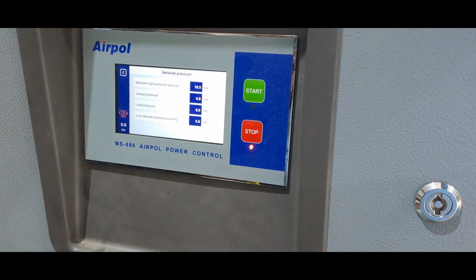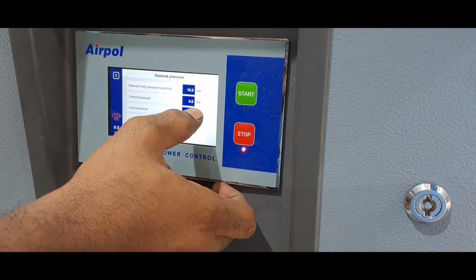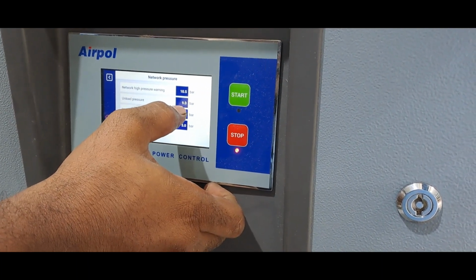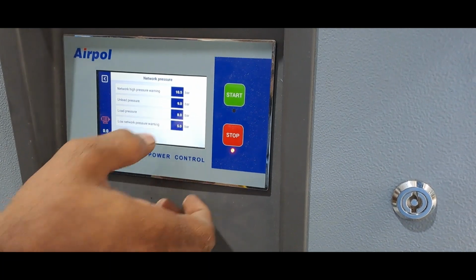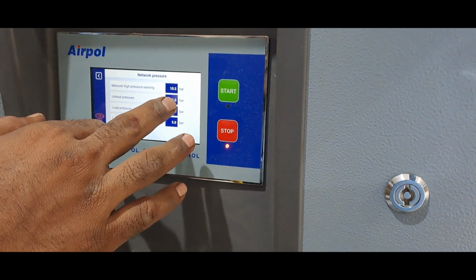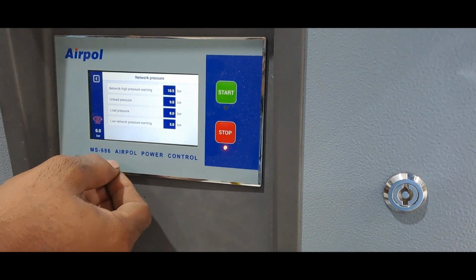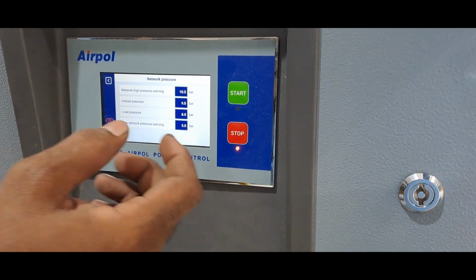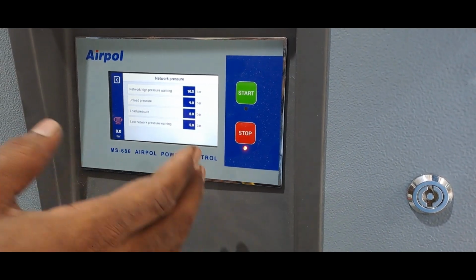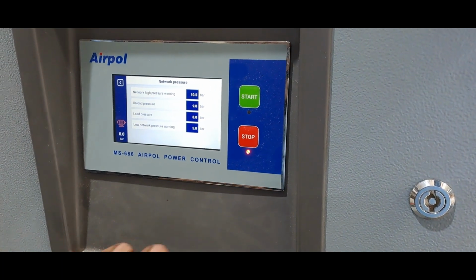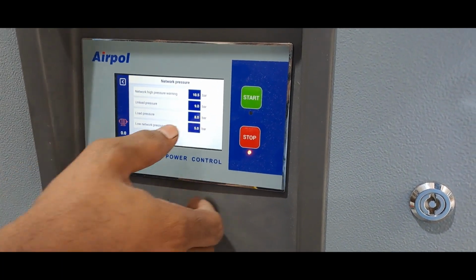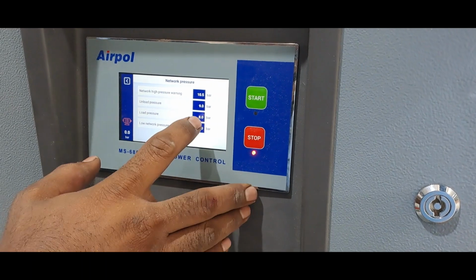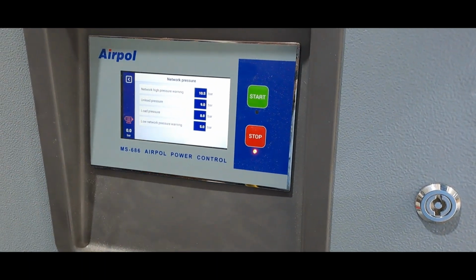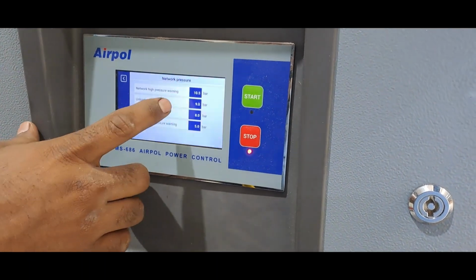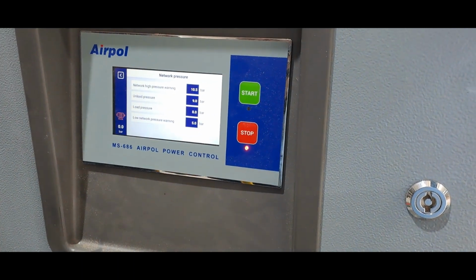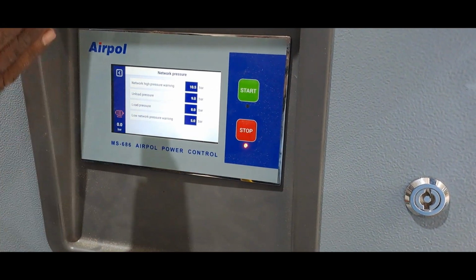The motor will be running in unload condition. And if there is no consumption after reaching 9 bar, and the compressor is continuously running at constant pressure in unload, there is some idle time set in this controller, like 1 minute 30 seconds. After that, the compressor goes to cut off, standby mode. And when the pressure again reaches 8 bar, the compressor will start again. Then it will go to 9 bar. This process will continuously go on from 8 bar to 9 bar.